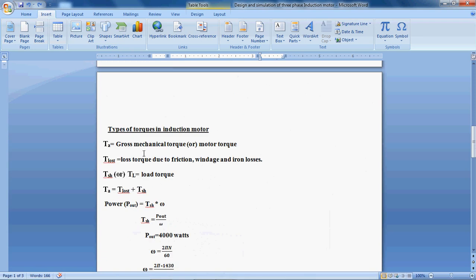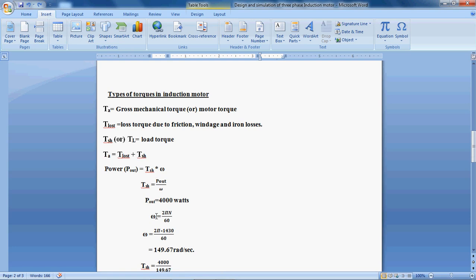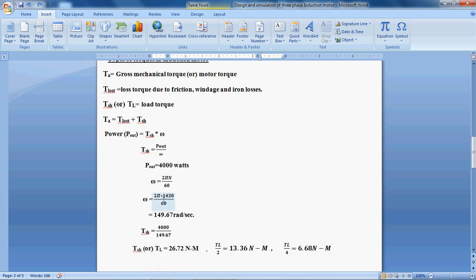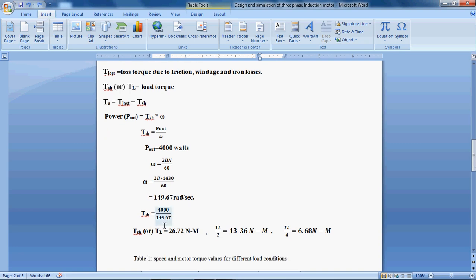You know there are types of torques in the induction motor: gross mechanical torque, loss torque due to friction, windage and iron loss, and shaft torque or load torque. Power P equals T into omega. For this preset model the power is 4000 watts. At speed 1430 RPM you get 149.67 radians per second. With this you can calculate the full load torque or shaft torque as 26.72 Nm. Half of the full load torque is 13.36 Nm and one-fourth of the full load torque is 6.68 Nm.